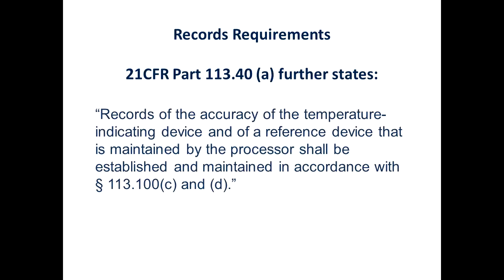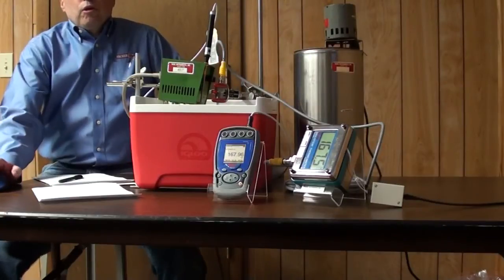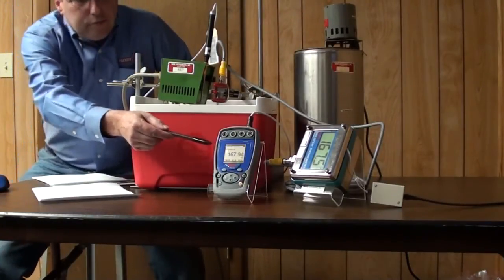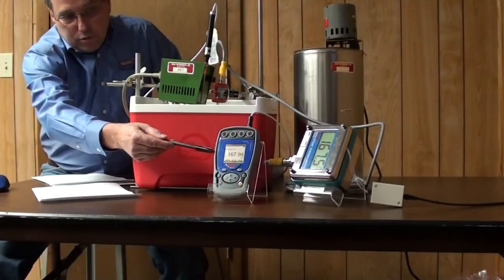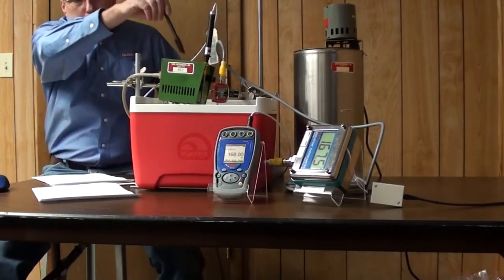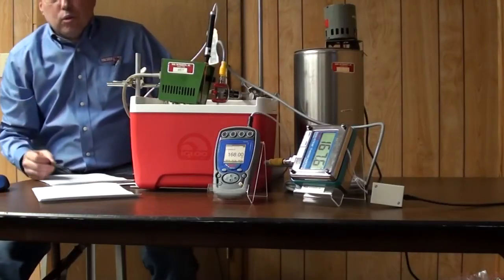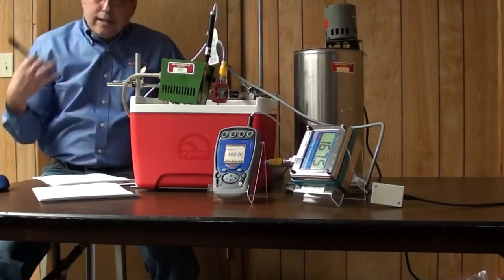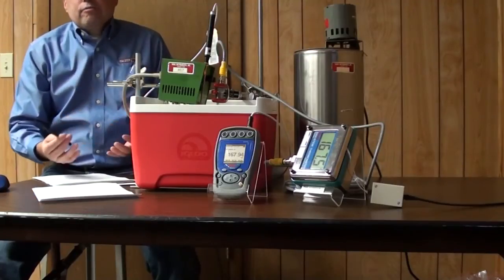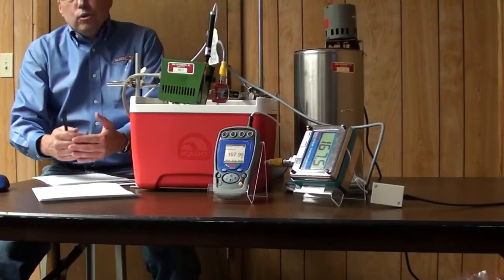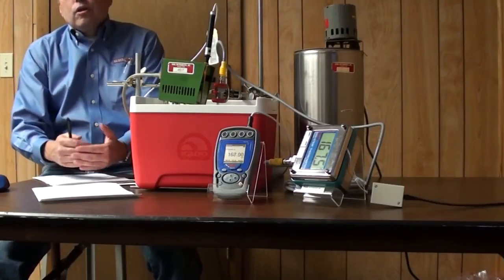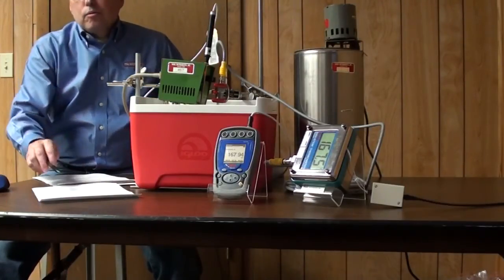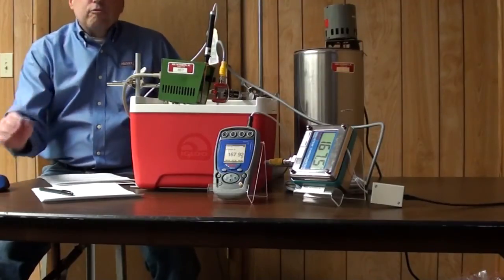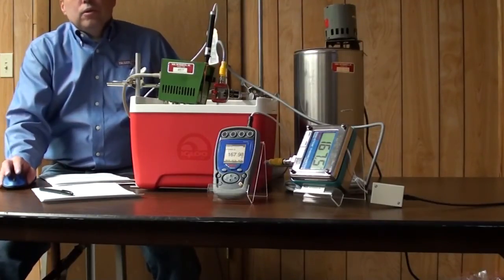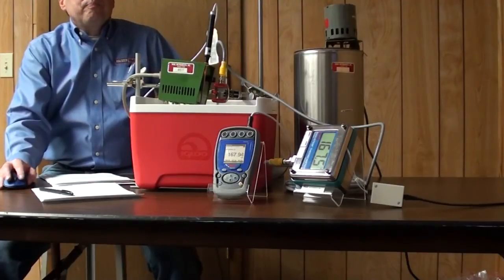Now, let me point out that where it says maintained by the processor, if you're using a reference device, like what I have here, a TM612, one of our meters, and a probe that I'm using as my reference device for the calibration we're going to do, you would most likely send that back to our lab to have calibrated. We're going to do the certificates and the data in accordance with that standard. So you would be getting that from us, but you still need to make sure that you hang on to those certificates and keep them.